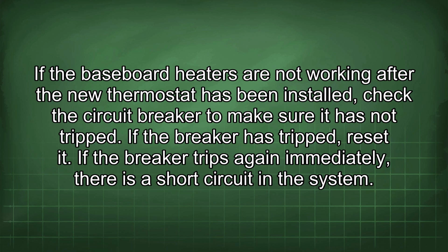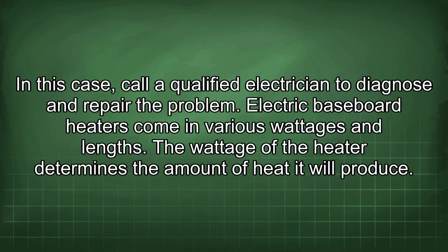If the baseboard heaters are not working after the new thermostat has been installed, check the circuit breaker to make sure it is not tripped. If the breaker has tripped, reset it. If the breaker trips again immediately, there is a short circuit in the system. In this case, call a qualified electrician to diagnose and repair the problem.